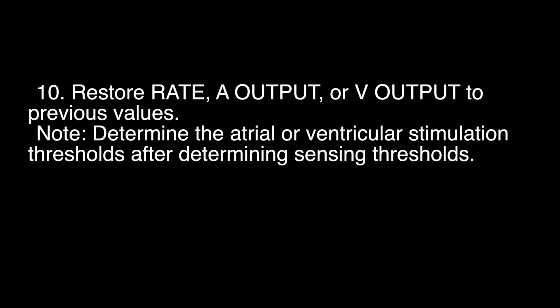9. Set sensitivity to half or less the threshold value. This setting provides at least a 2:1 safety margin. 10. Restore rate, A output, or V output to previous values. Note, determine the atrial or ventricular stimulation thresholds after determining sensing thresholds.